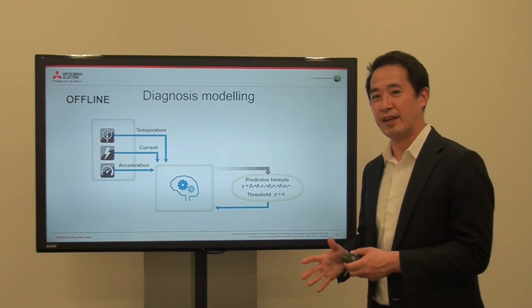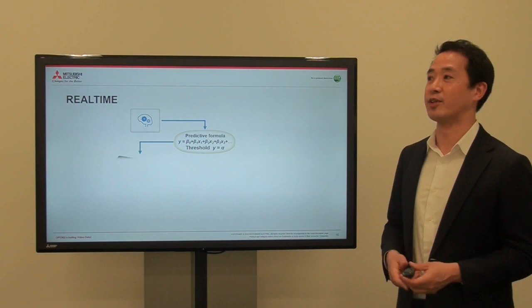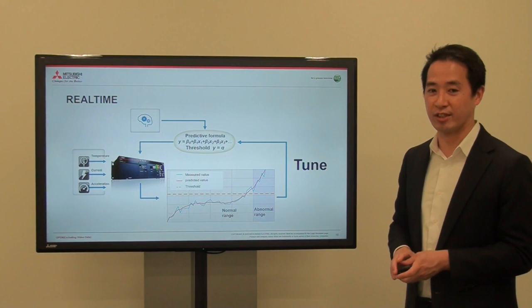The threshold means: if the gear wear rises to a certain level, we want to send out an alarm to alert the worker to stop the machine. So we create both the predictive formula and the threshold, and we actually take this predictive formula and test if it works. We put this in the actual machine, put it in an edge computer, collect the actual data, and then produce the chart.